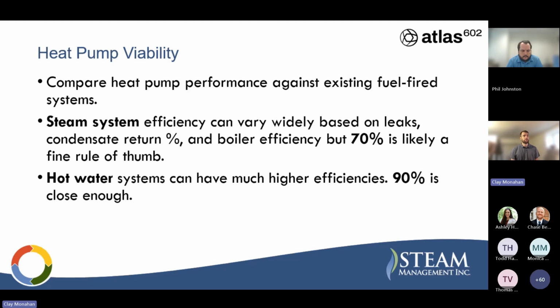Phil's got good stuff lined up, but in the industrial setting, just starting on the more utility-based systems, if there's things like chillers or an ammonia refrigeration system, you're not going to see temperatures that high, or at least certainly not average temperatures that high. So you'd have to go to things like hot exhaust sources from a dryer, or existing boiler operations or a CHP unit. Those exhaust sources are going to have significantly higher, not just dry bulb temperatures, but wet bulb temperatures, which really drives the heat available calculation. Okay. And like you say, Chase, we're going to get more into that later.